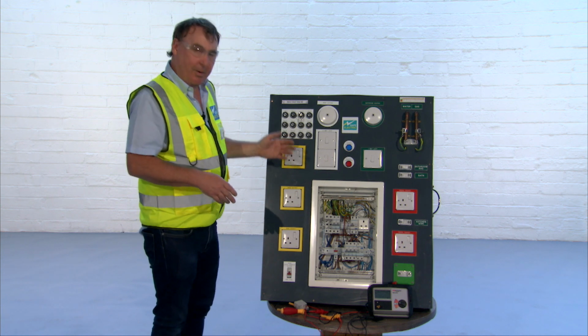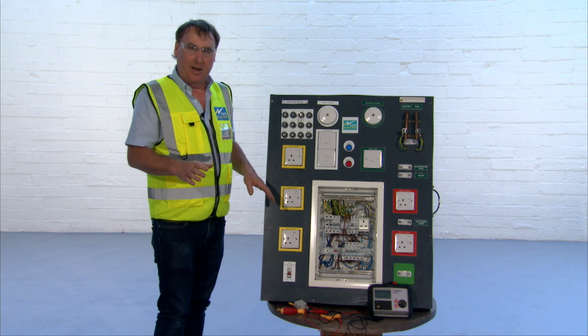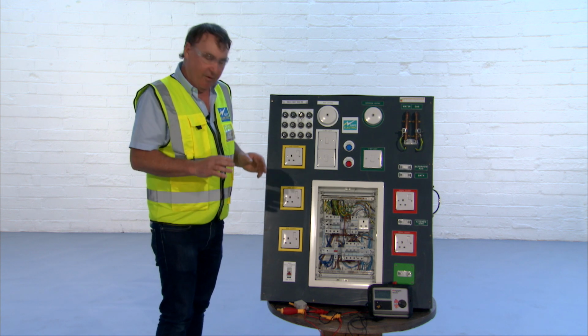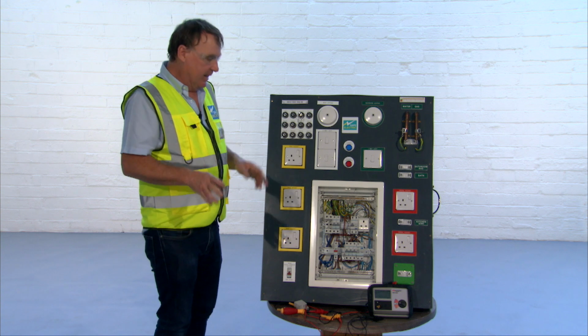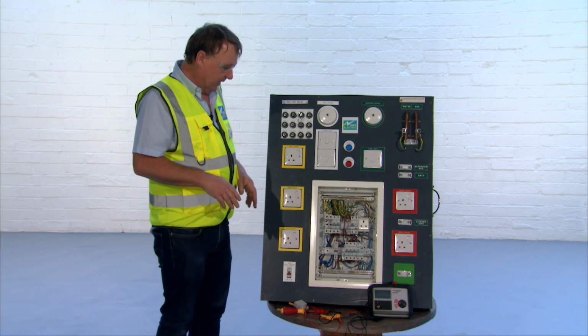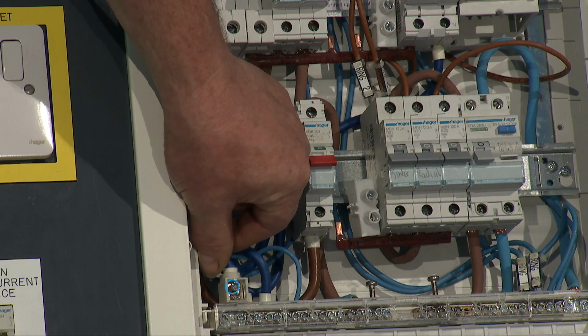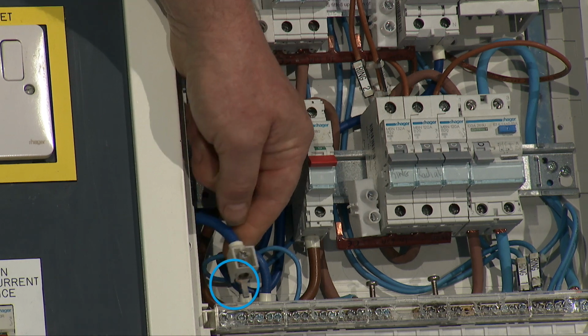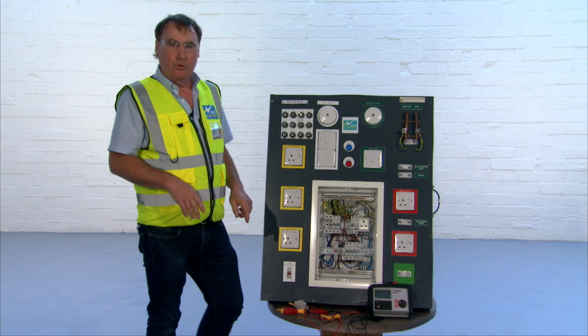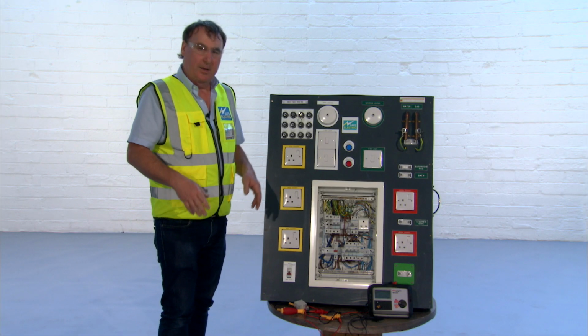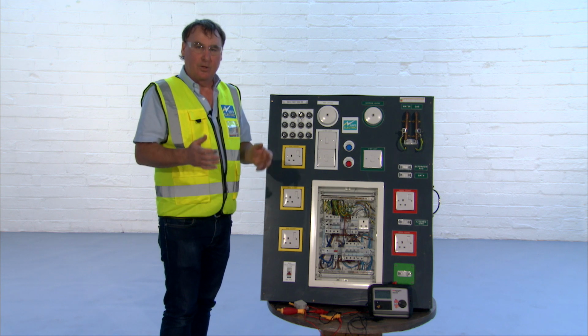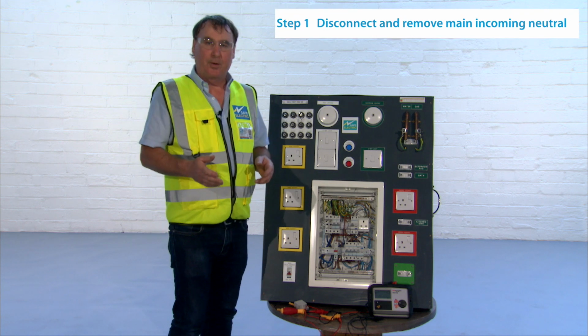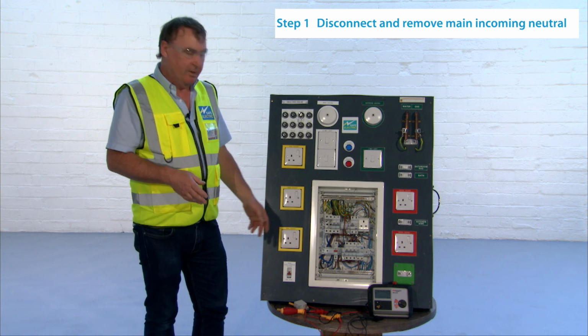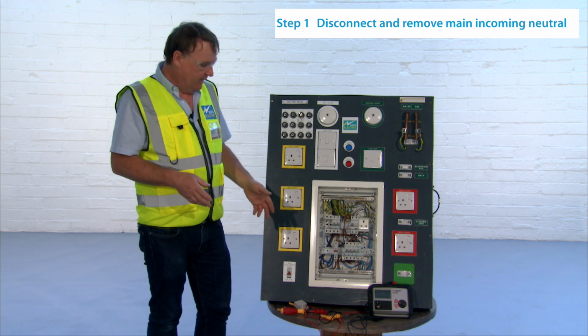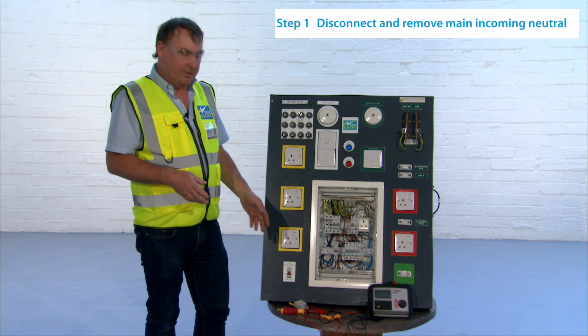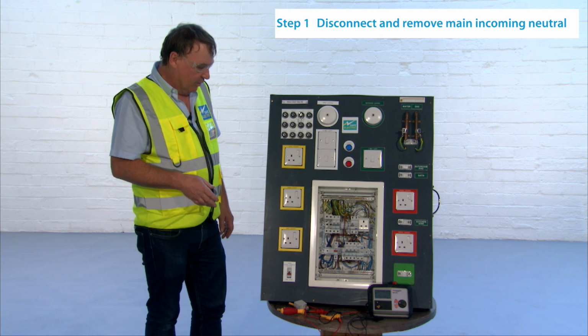Step number one, and the power is off on this board at the moment, it's never been energized, it's a dead installation, or if it's an existing live installation, it's switched off at the main overcurrent protective device. Step one, we're going to remove the main incoming neutral, which is a 16 square blue, from the neutral bar. The purpose of this step is to disable temporarily the neutralizing link. It should not be required to carry out this step in a new installation because the neutralizing link has never been created. But in an existing installation, it is important to remove the main neutral.